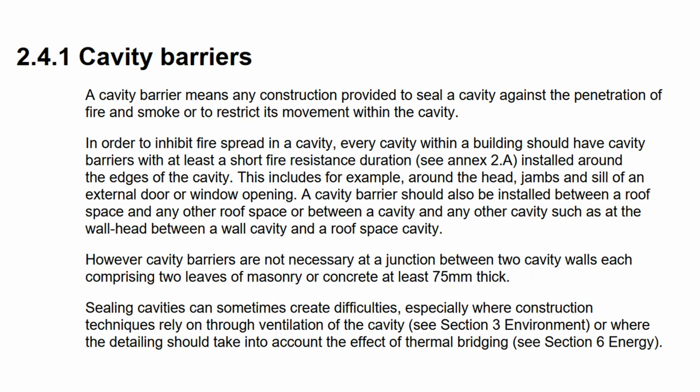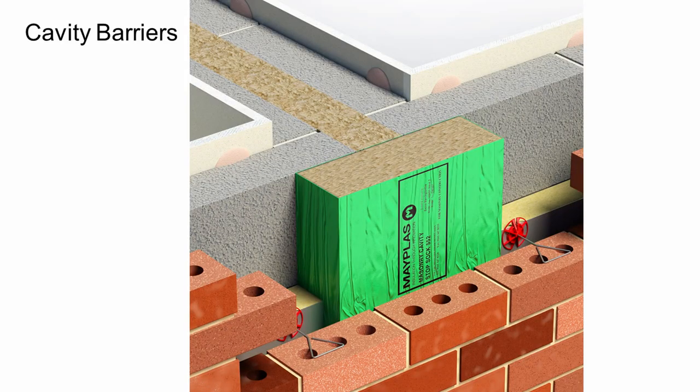A cavity barrier is slightly different from a cavity closer. A cavity closer can mean something that's not fire rated that closes off a cavity, whereas a cavity barrier is specifically designed to inhibit the spread of fire. Usually they are a mineral wool product, wrapped in a plastic sheet, designed to fill the whole gap between two layers of masonry. Because they're made of mineral wool, they do participate within the insulation envelope of the building, so it's not a significant break to move from one insulation to the next when installing a cavity barrier.